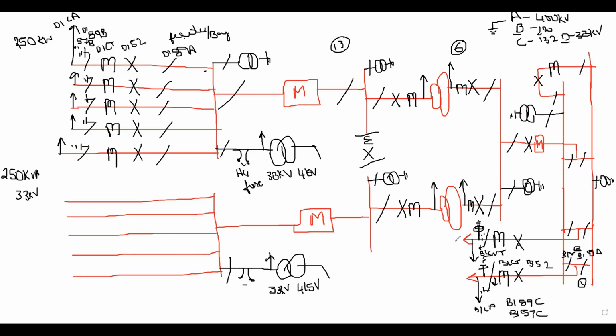So this is my representation. Regarding this representation, for A and B, base side A or line side B, is there any fixed standard or not? You can choose. You can choose 89A, 57A, and this is 89B. But the rest, the 89, 52 and 57, will be as per standard. Yes. 89 means isolator. It's an ANSI code. 52 is breaker.